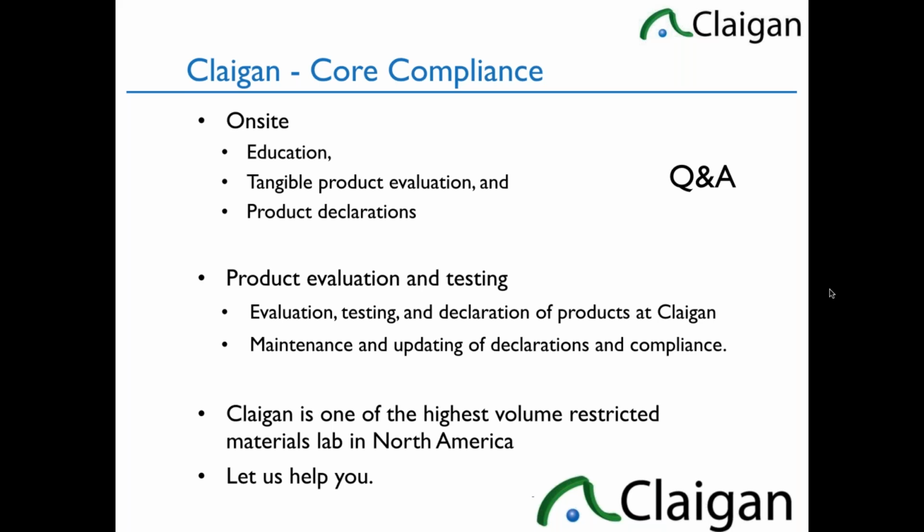So with a few exceptions, almost every chemical that's reasonably likely to be in the product, outside really exotic products like stents and some of the coatings on stents, outside of some real exotics, but things you're more likely to know what's in it, you're really looking at RoHS, REACH SVHC, Prop 65 substances, plus a few others, beryllium and a few others, beryllium copper. But it is far more manageable.